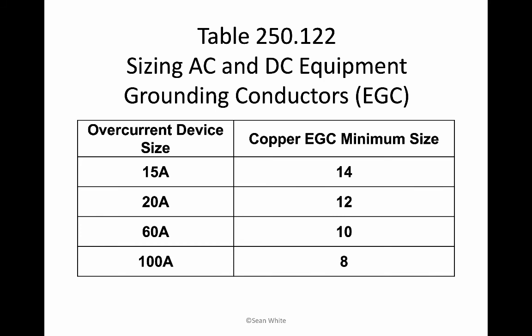In fact, in theory, you could have 100 10 gauge wires running off of your roof to 15 amp fuses down below, going to a bigger inverter, and have one single puny little 14 gauge equipment grounding conductor going with those wires, and that would be compliant with the National Electrical Code, and that would be a big enough wire to carry the signal that there's a ground fault, but probably nobody would do that.